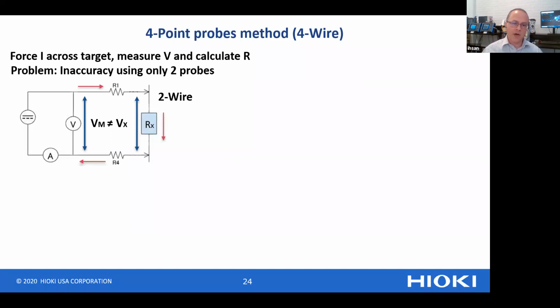And the problem here is that the voltage drop across the target, which is Vx, is not exactly the same as the voltage that's measured by the voltmeter, because we have a current flowing in this circuit, and the resistances R1 and R4 represent the contact resistance and also the test lead resistance. So they cause an IR drop. So this is not an accurate way of testing.